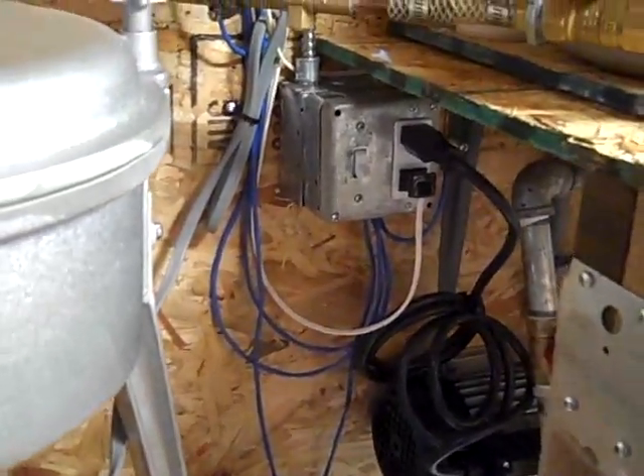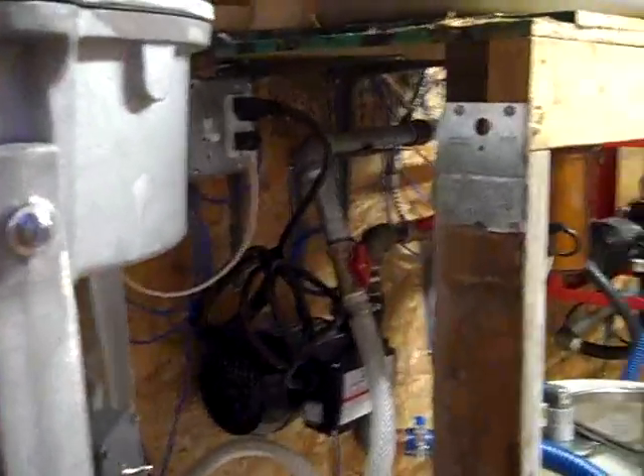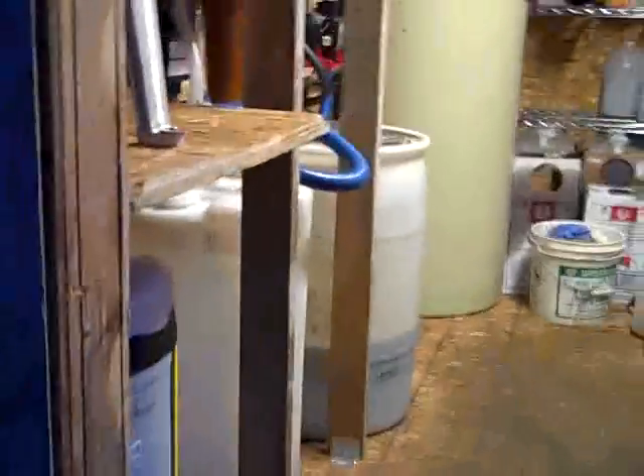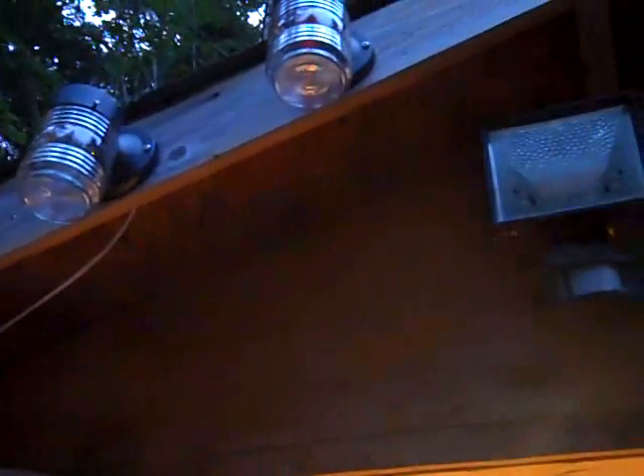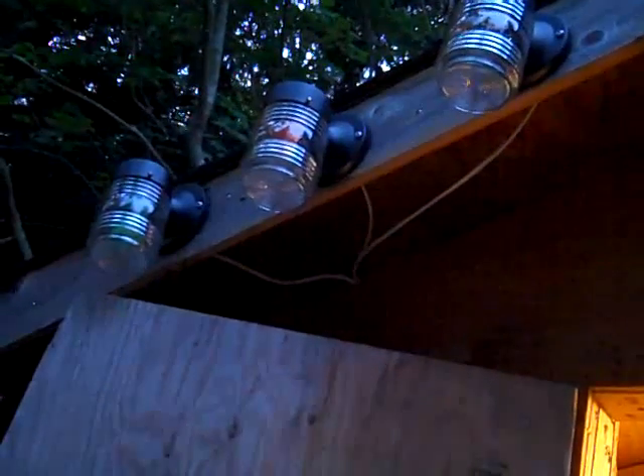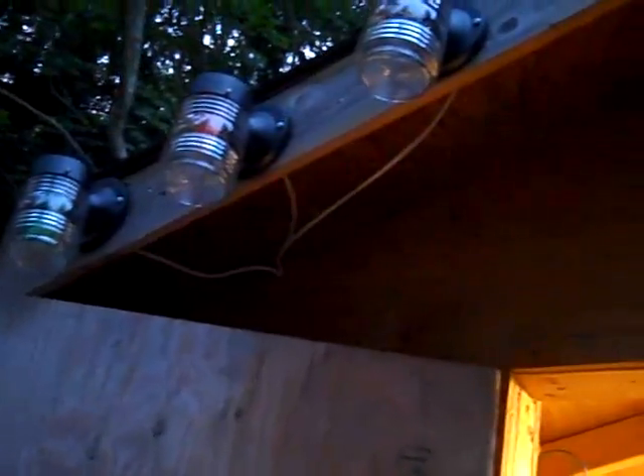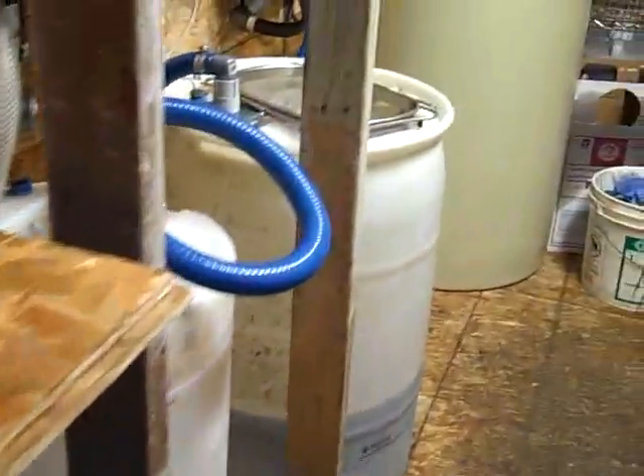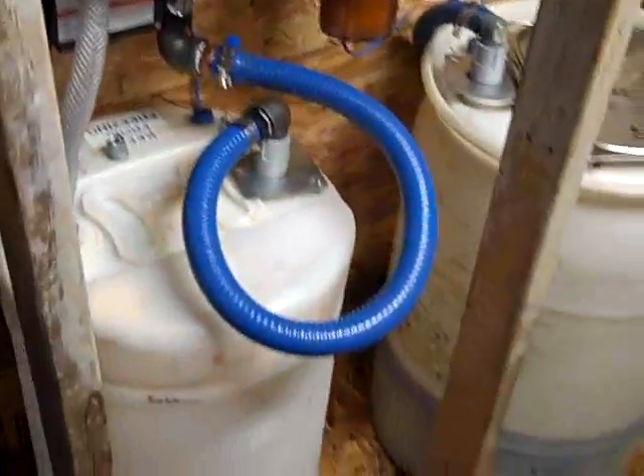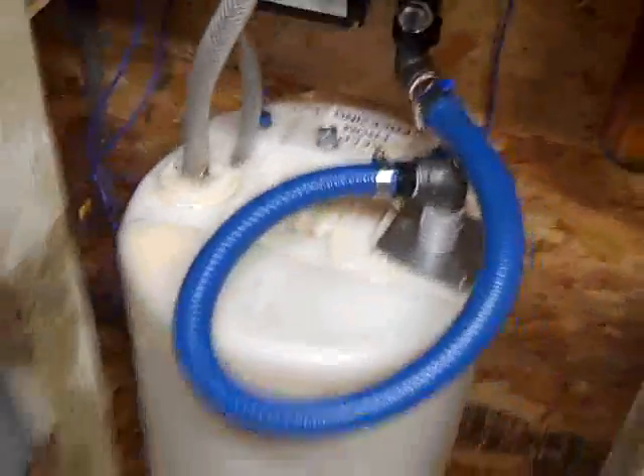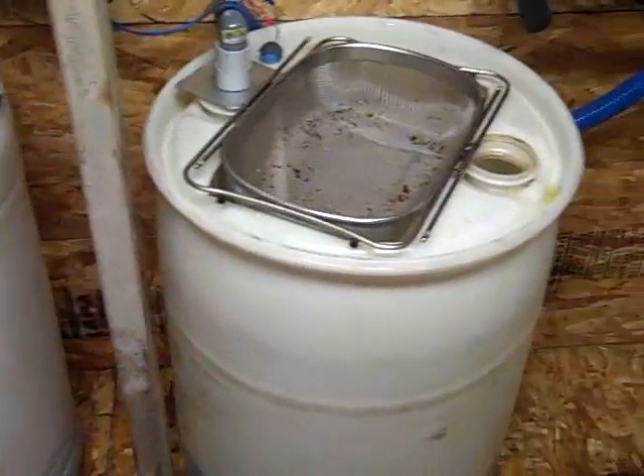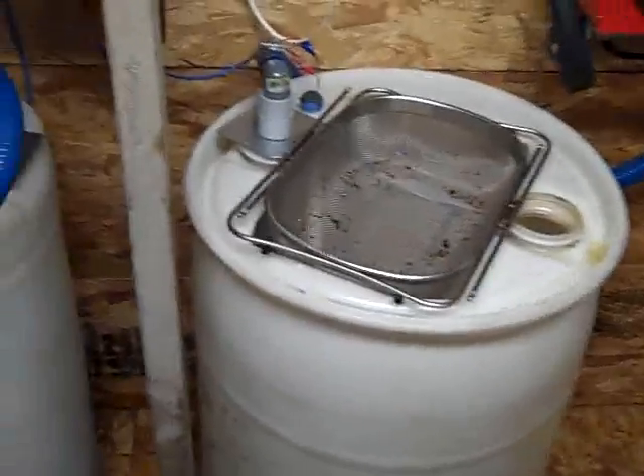What I also did on this particular system was I put what I call operating lights on the outside of the fuel center. And what we have there is 4 operating lights. Depending on what pump or centrifuge is running, it will control either light. So this gives me a visual for when I'm not in the fuel station here, that I can be out and about and just look and see what is running, what is not, and if it appears to have been running for an extended period of time and it shouldn't have been, then I can come and check on it and see what's going on.